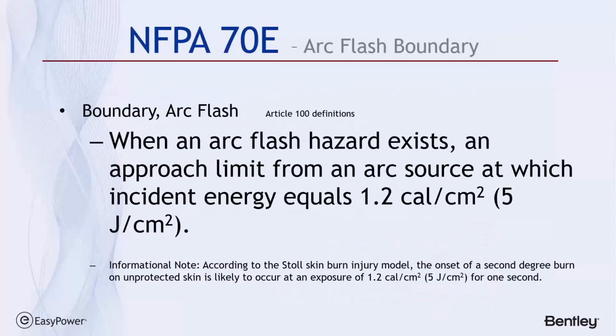Which brings us to the definition of an arc flash boundary. And in Article 100, the listing of the definitions, the arc flash boundary exists when an arc flash hazard exists, an approach limit from an arc source at which the incident energy is 1.2 calories per square centimeter is defined as the arc flash boundary. Now, these just aren't random numbers. The 1.2 calories per square centimeter has been determined to be the potential onset of second-degree burn on unprotected skin for 1 second. And that turns out to be a very low arc flash event that produces energy less than 1.2 calories. That happens.